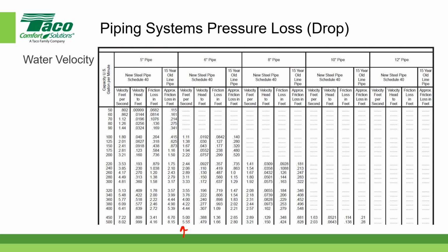So you can see that in this table, they came out with the 5.55 feet per second. And that's exactly the same number that we calculated. So it's good periodically, if you're using a table or an app on your computer or an app on your phone, to do a simple calculation to make sure that the values that you're getting, and in this particular case, the first value that we're looking at is the velocity, is the same as what you can calculate. The value that you can calculate is the same as what's being published, and then you have some confidence that the published data is correct.